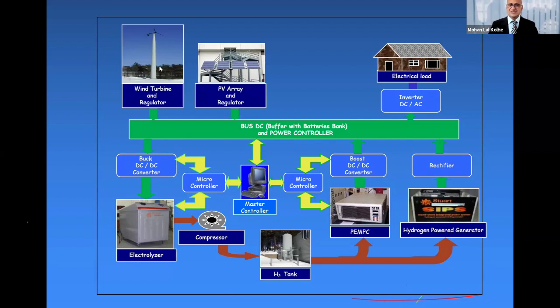Similarly, this wind turbine was a permanent magnet synchronous generator, meaning it was producing variable voltage, variable frequency output, which we cannot supply directly to the DC bus. So for that we need some regulator or power conditioning devices. That's very important here.